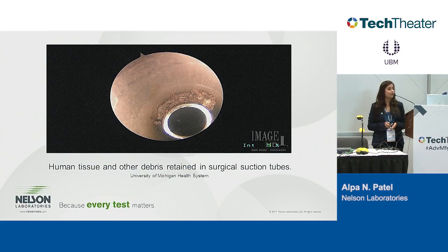This is an example of a surgical suction tube that had debris in there. People thought a long time ago that if you skip cleaning and just do sterilization or disinfection, we're still fine because we're killing the bacteria. That is what causes infection. So why are we so worried about this cleaning aspect of it? But the reality is, if there's any debris, guess what? It's not getting cleaned and it's not getting sterilized or disinfected. And then the debris will be impacted over and over and over again, causing bacteria to hide in those areas, and you can't sterilize or disinfect them, and that's where the outbreaks happen.